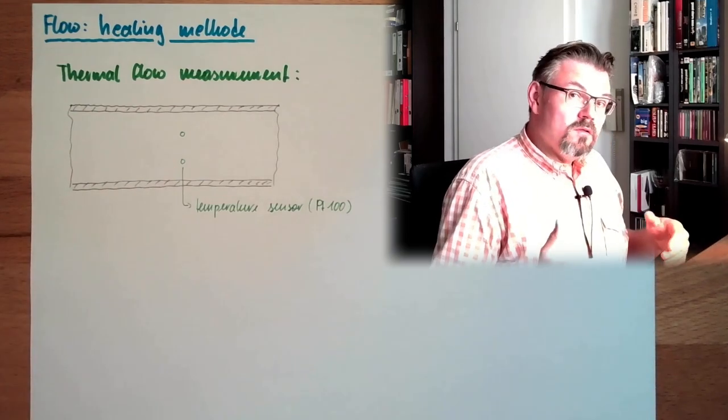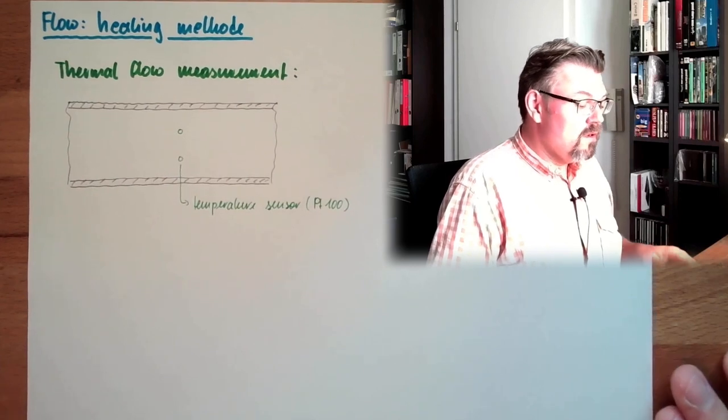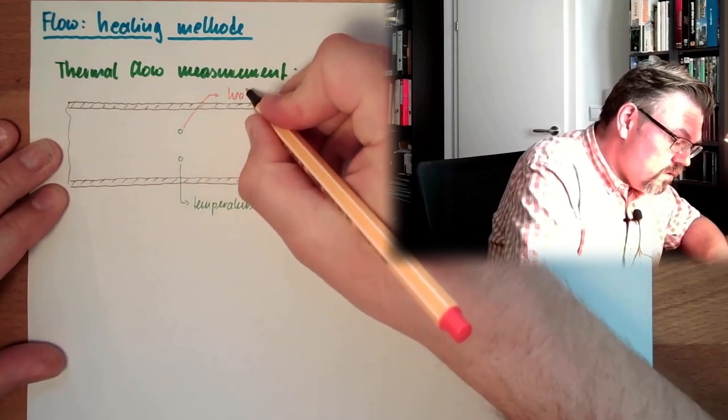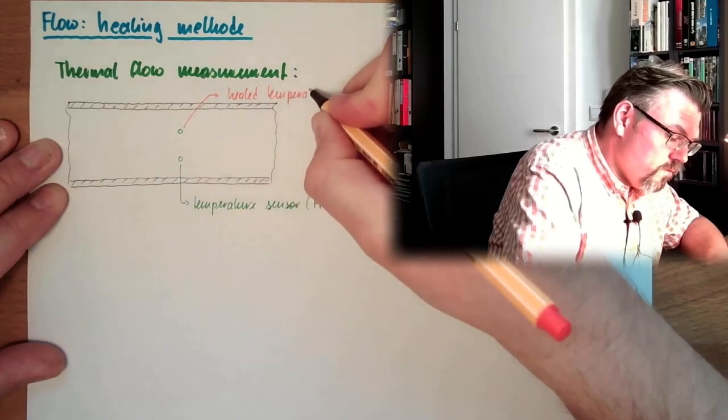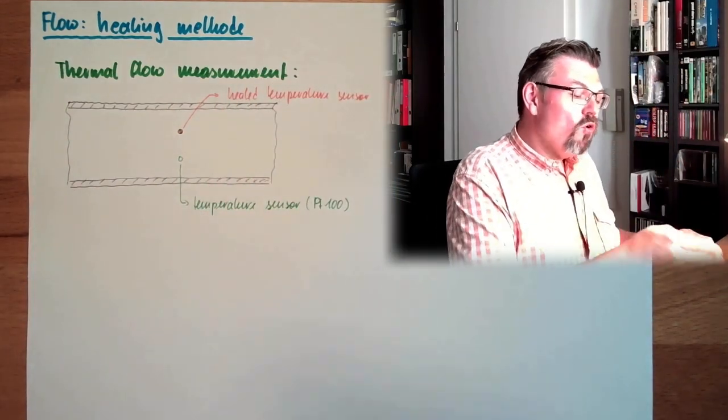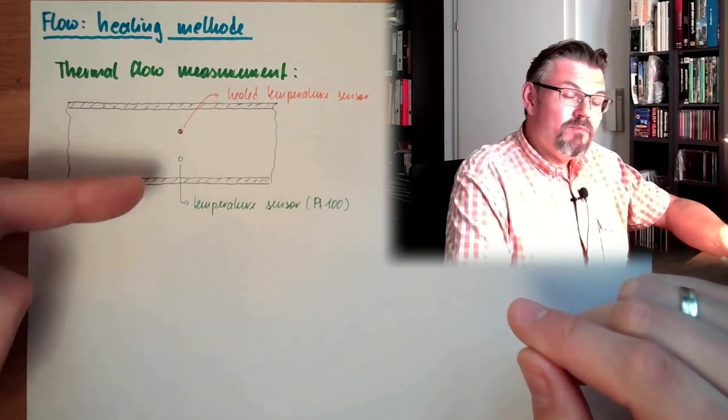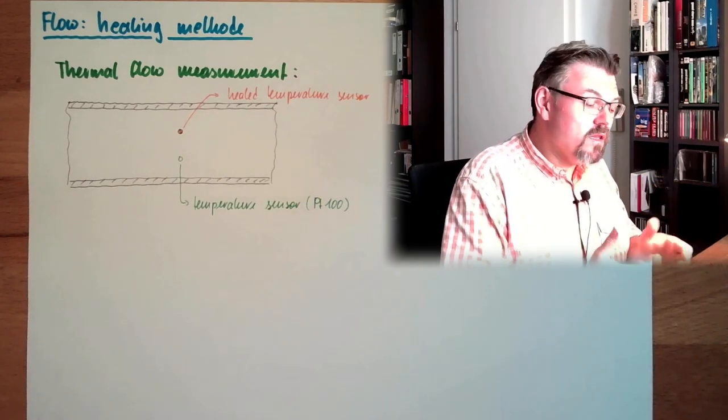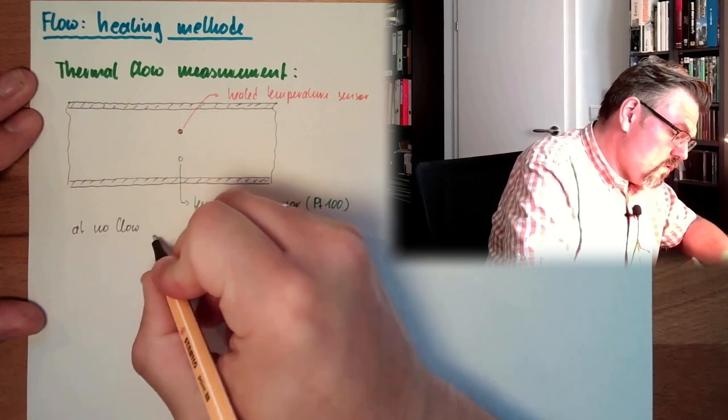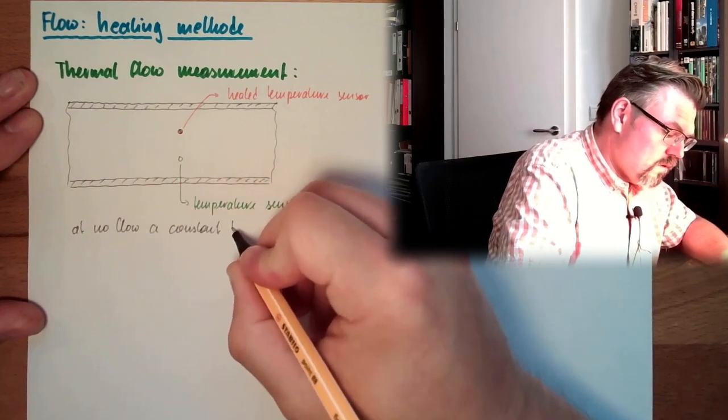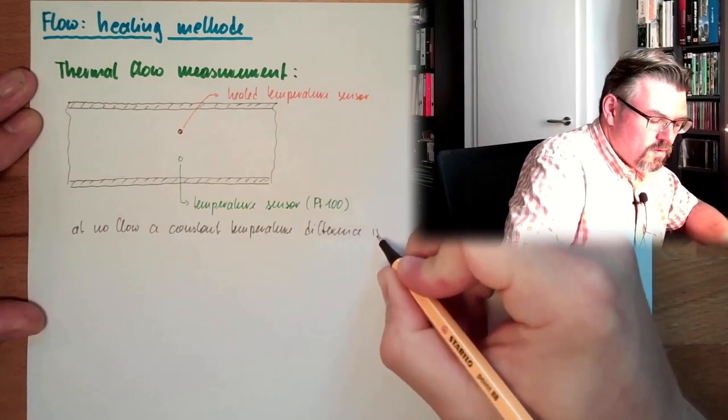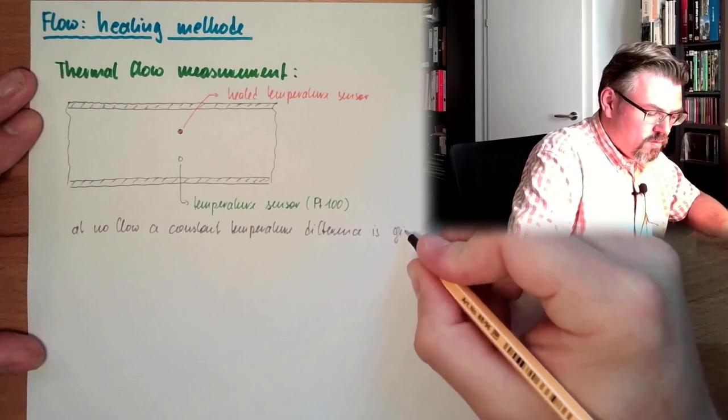Now one is measuring the actual temperature of the gas or the liquid in there, and the other one is heated. So this one is a heated temperature probe. If there is no flow at all, there will be a certain temperature difference depending on the heating power. So at standstill or at no flow, a constant temperature difference is given.